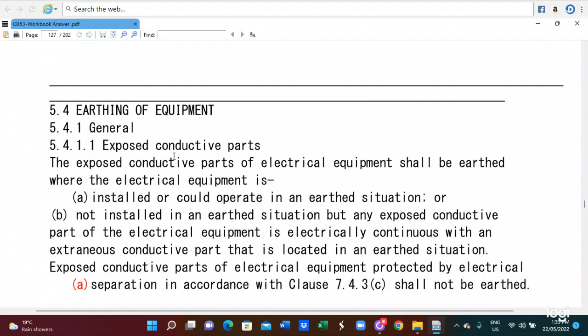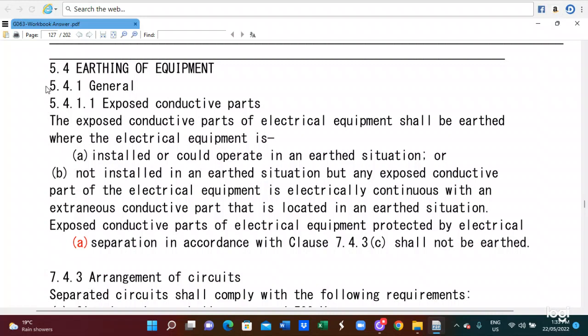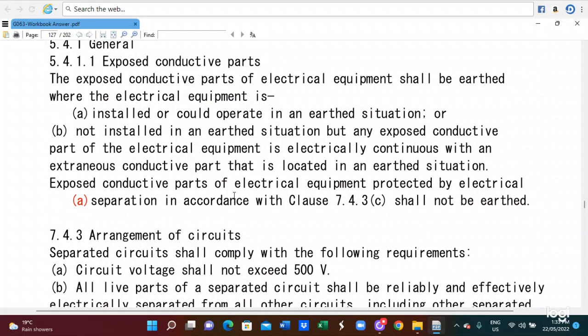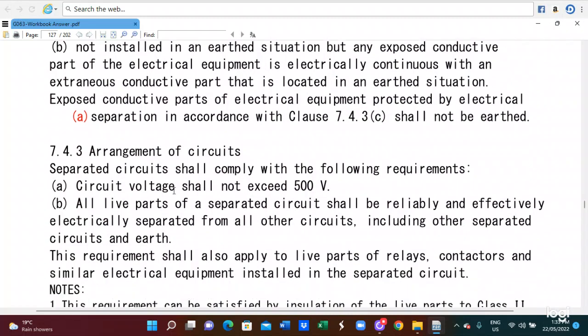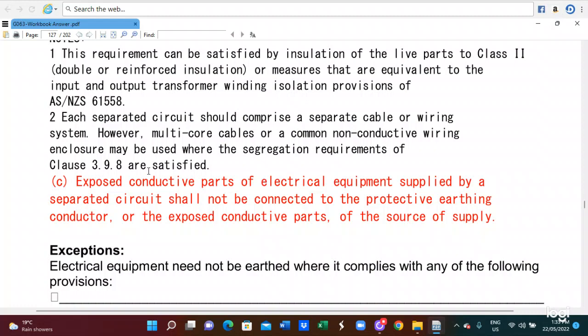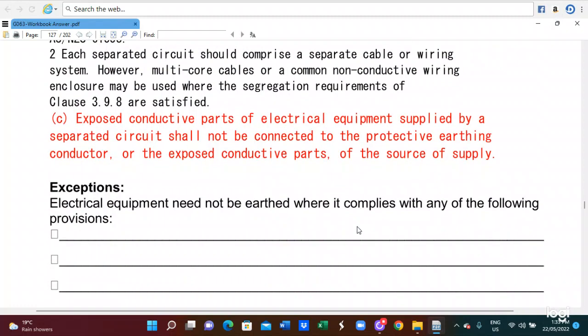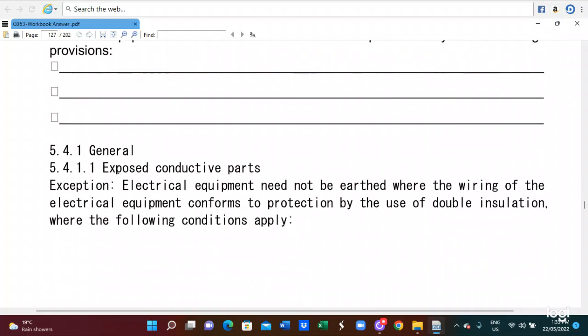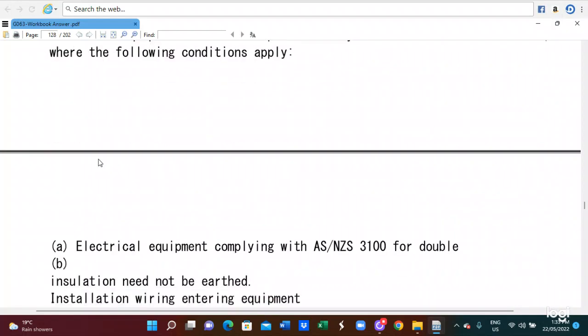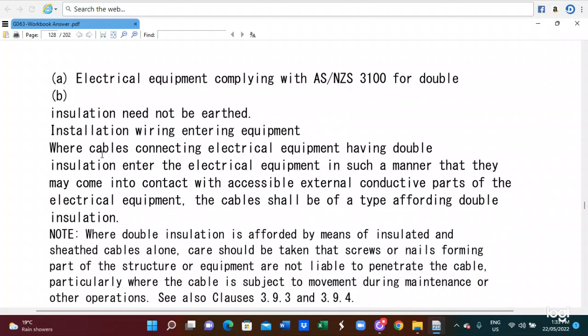And earthing of the equipment, you can also see 5.4.1. So earthing of the equipment to install. And 7.4.3 is arrangement of the circuit. Exposed conductive power electrical equipment supplied by a separate circuit shall not be connected to the protective earthing conductor or the exposed conductive part at the source of the supply. And 5.4.1 is an exposed conductive part information. Electrical equipment shall comply with the installation standard. You can also read into this one.